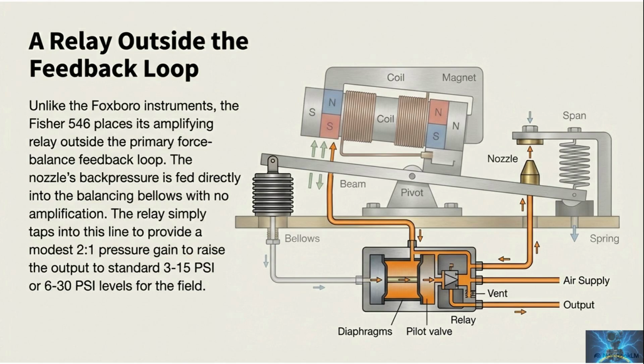A relay outside the feedback loop. Unlike the Foxboro approach, the Fisher 546 places its amplifying relay outside the primary feedback loop. The nozzle back pressure goes straight to the balancing bellows, with no amplification in that core loop. The relay taps into the signal line and boosts it with a modest 2-to-1 pressure gain. That boost brings the output up to common field standards like 3 to 15 pounds per square inch, or 6 to 30 pounds per square inch. This is a great reminder to always trace where the relay sits before you assume how the loop behaves.